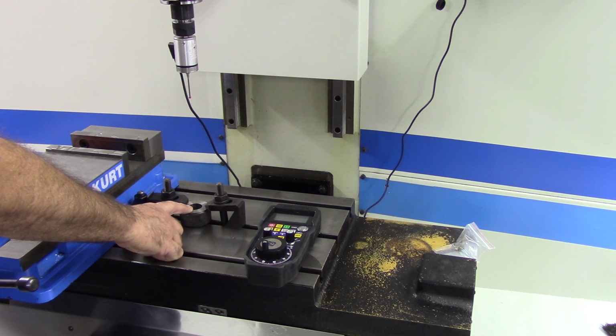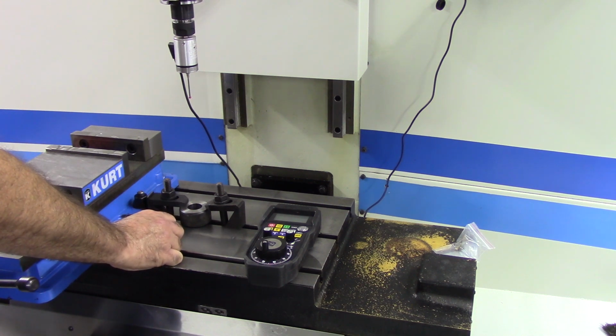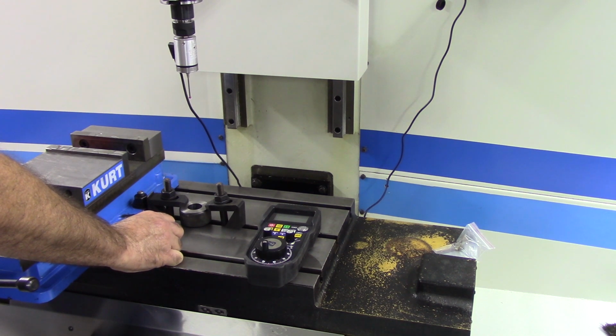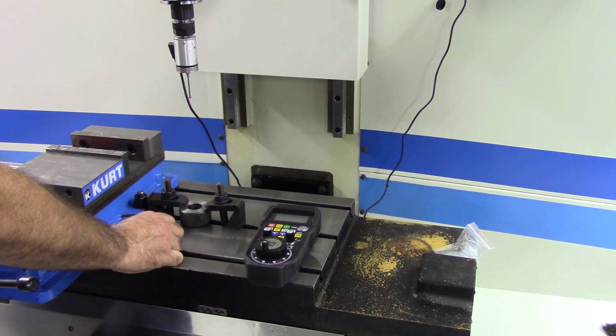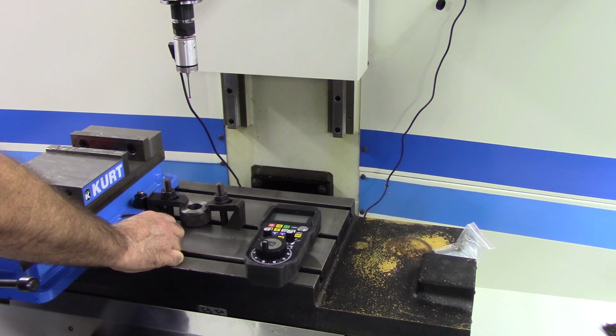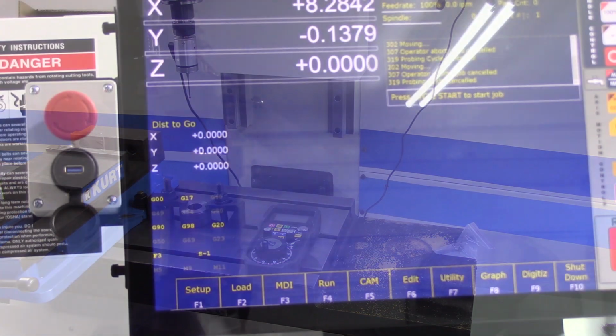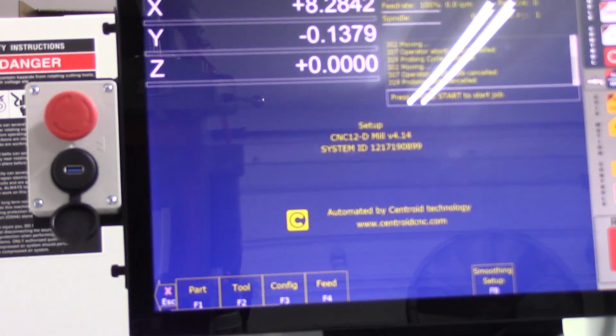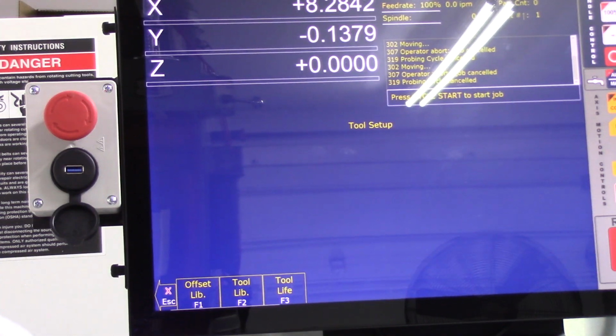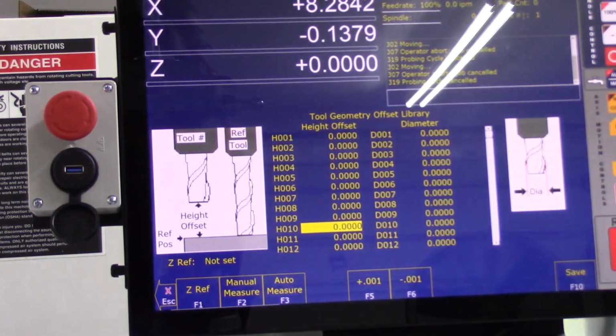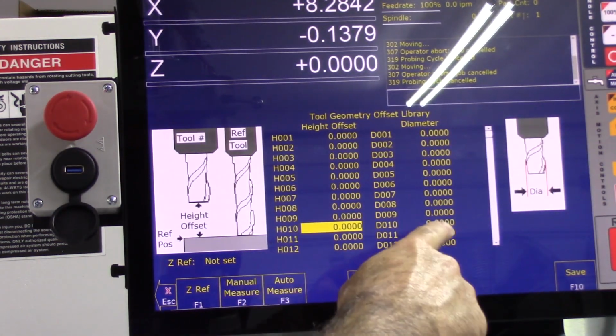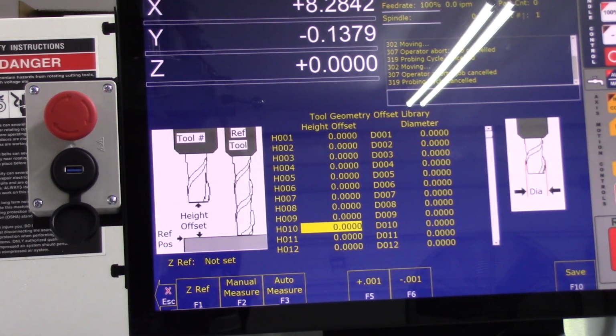Fix your precision ring gauge on the machine tool. The ring must lie flat. Make sure the probe is plugged in and working. We just did that. Go to the tool library offset menu and set the diameter for the probe tip to 0.000, in our case for tool 10. So we set diameter 10 to 0.000. We're going to go F1 setup, F2 tool, and then we'll go to offset library, and our diameter is 0 right now.